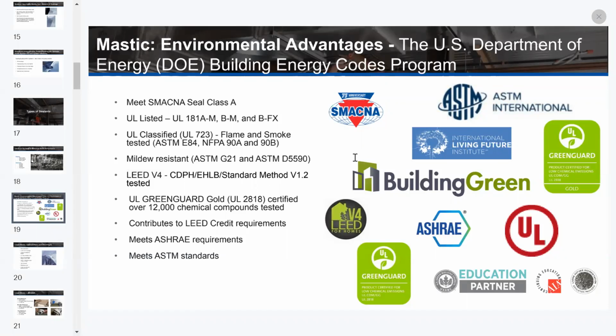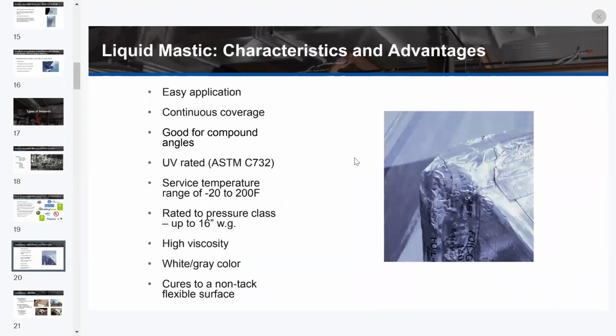For example, there's an aerosolized adhesive product that does not actually meet the UL and SMACNA requirements and can leave a residual tack in the duct system, which, if you think about it from an indoor quality side, is probably not a good practice. So it's basically at the end of this slide talking about really pay attention to what you're specifying. All right, moving on. Thank you.